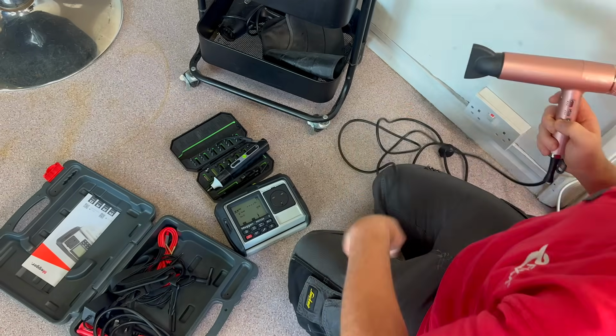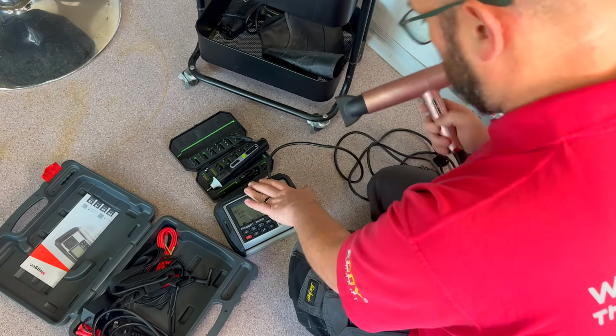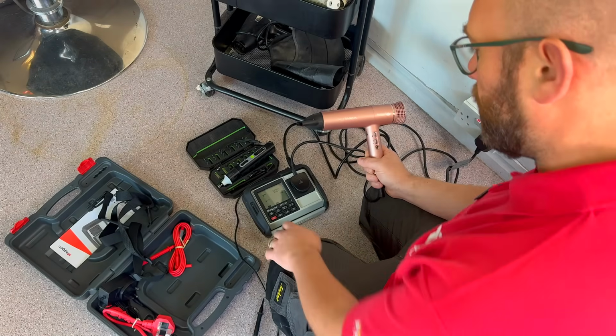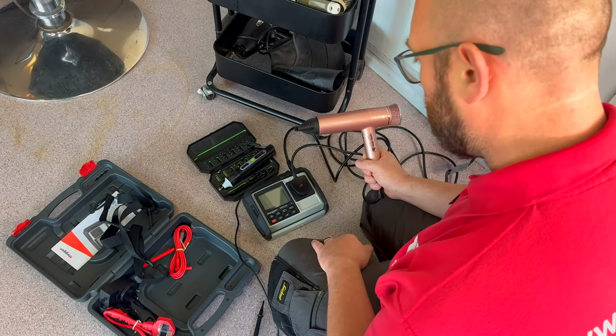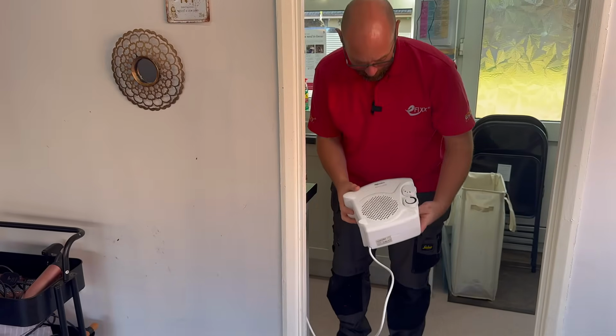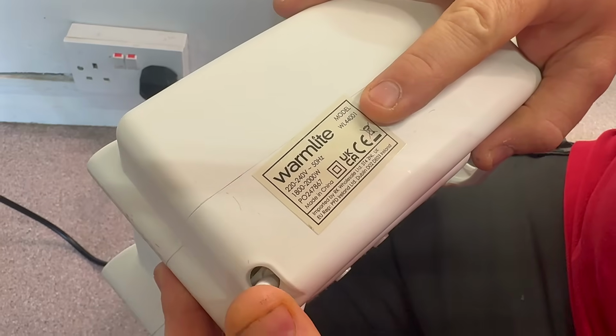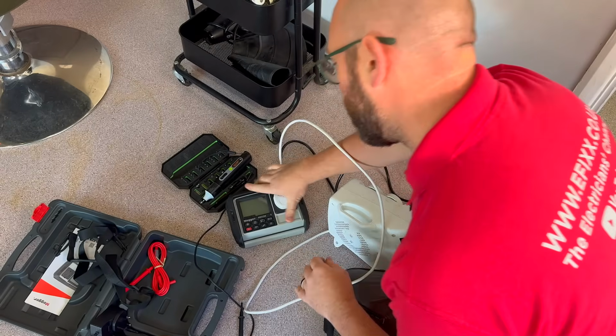So the only test needed for this is an insulation resistance test. As the Megger PAT250 tests between live conductors and earth, then the risk of damaging any components inside is minimal. We also need to make sure that the appliance is switched on, so the test goes to the very end of the appliance. This portable heater is also class 2, so I'm going to test it at 500 volts DC. Again, it's important to make sure that the heater is on.